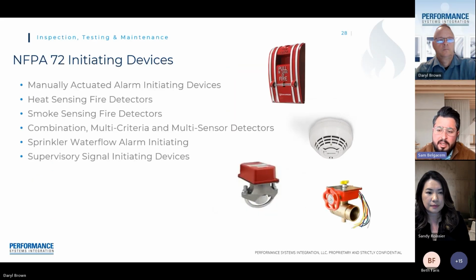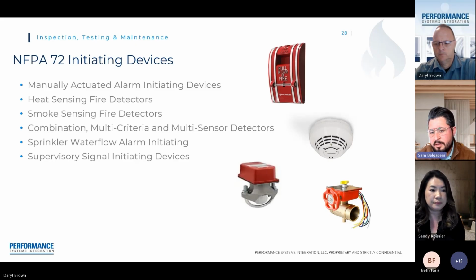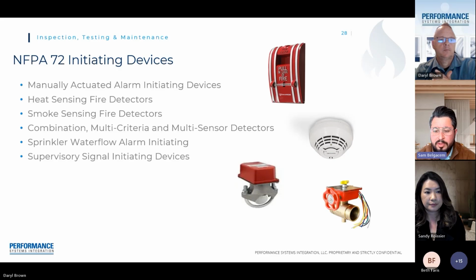So the operation starts with the initiating devices, and as I mentioned, there are some electronic ones like a heat detector, smoke detector, flame detector. There are also some components of the fire alarm that are related to the sprinkler system, like the water flow and the tamper switch. So in case the sprinkler goes off in a fire, the water flow will detect that and notify the control panel to do its work.